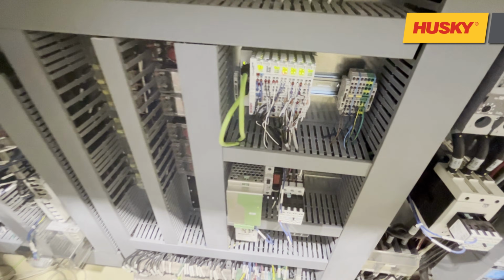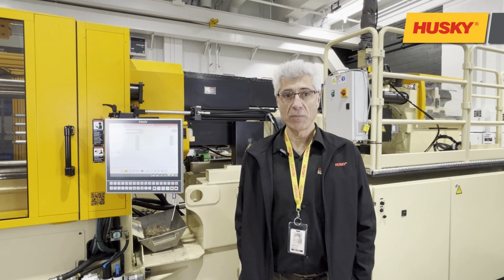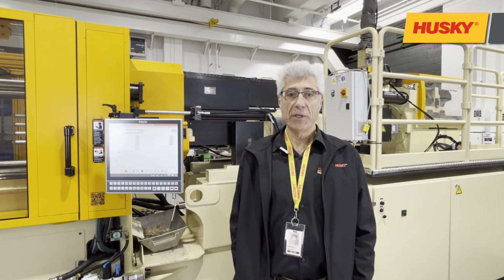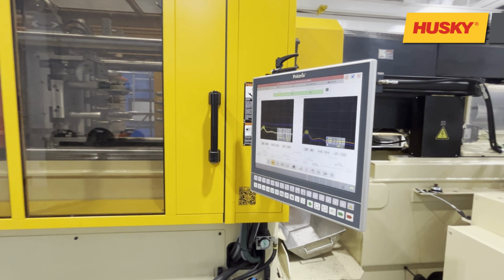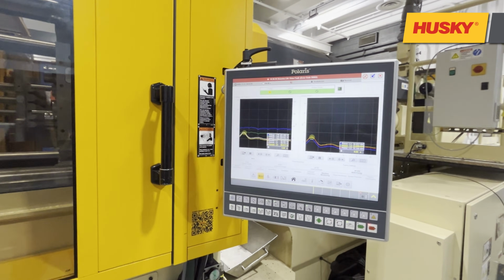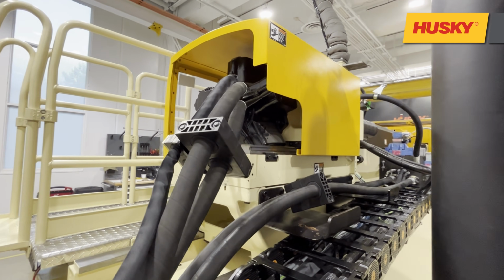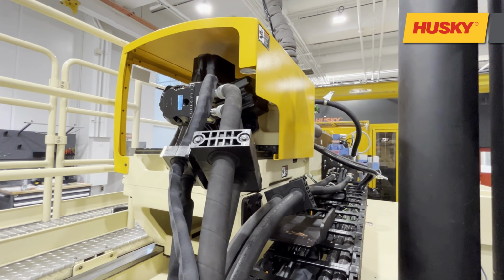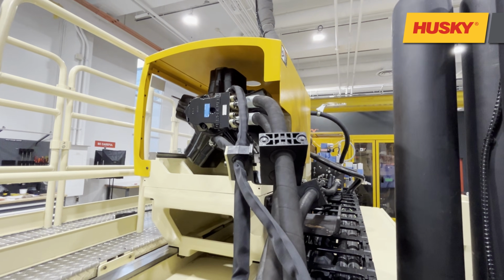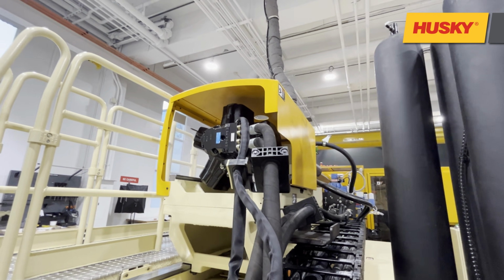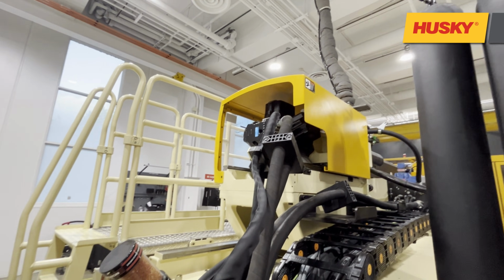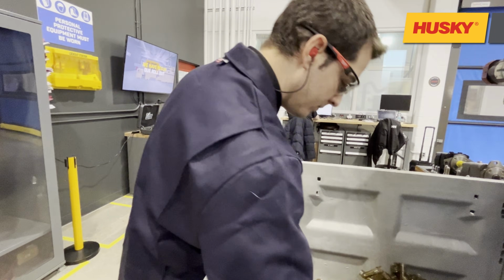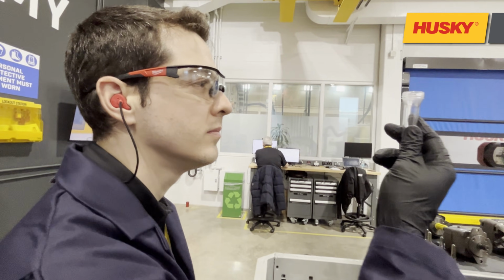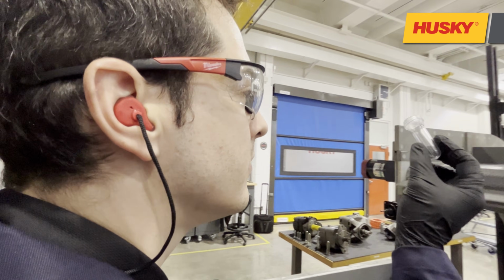Second, it tracks the load on the pump motor during production. If the motor is overloaded, operators get an alert, giving them a chance to fix the problem before it leads to a major issue. Third, it detects underlying hydraulic problems, such as excessive internal leakage or degraded pumps. Early detection prevents premature oil degradation and avoids the extra energy consumption these issues usually cause. And when you combine motor monitoring with accumulator monitoring, you get a complete view of your machine's power pack health, making preventative maintenance a routine, not a reaction.